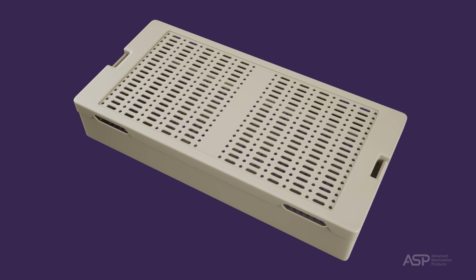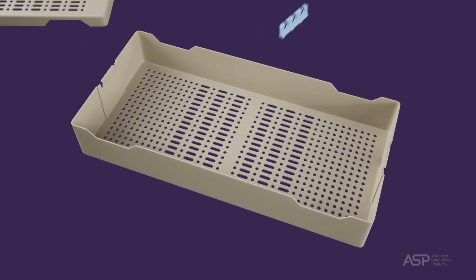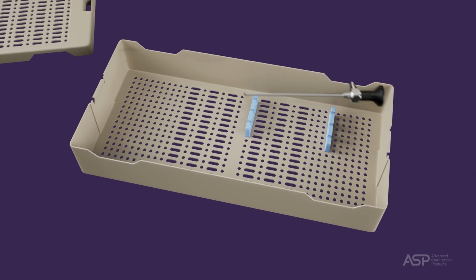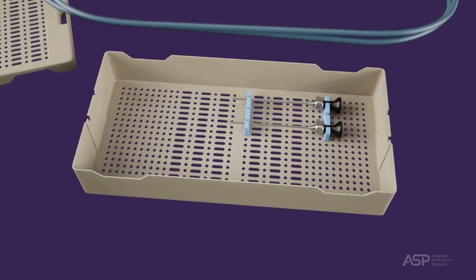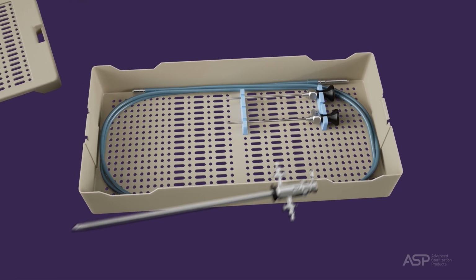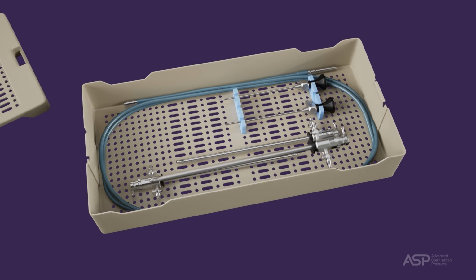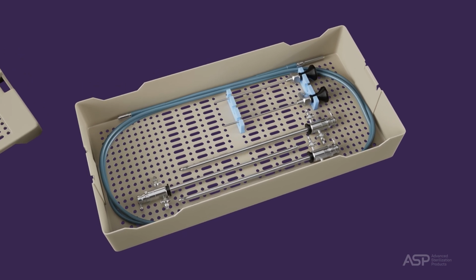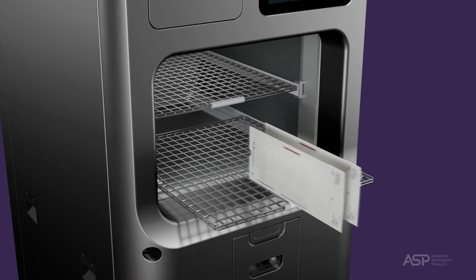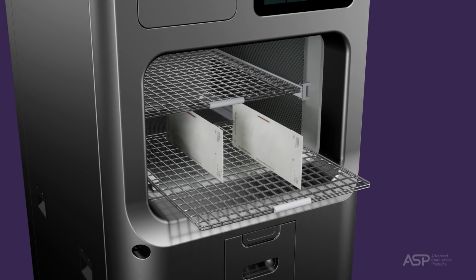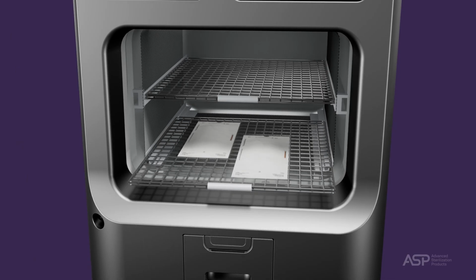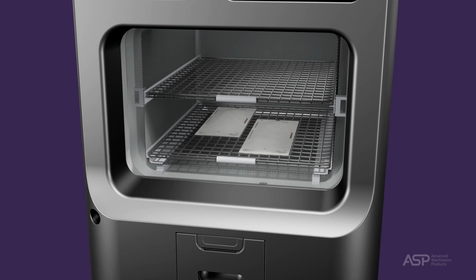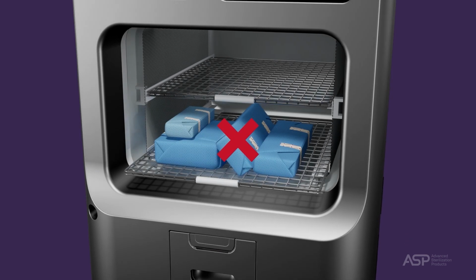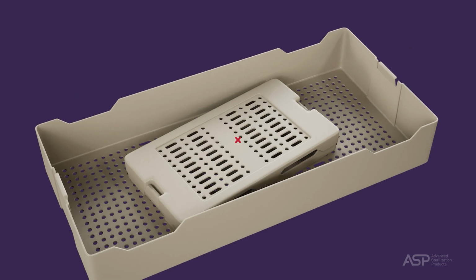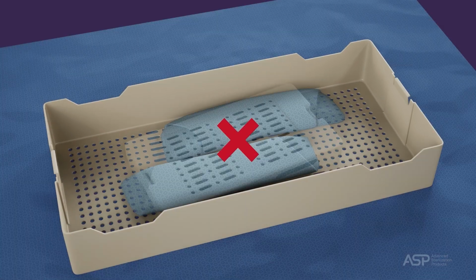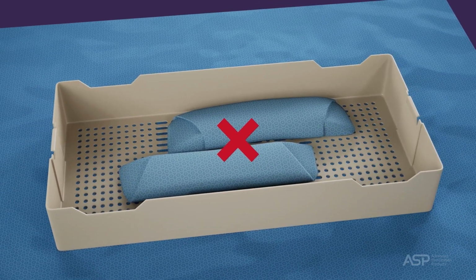Detailed information on loading and packaging can be found in your user's guide, but the following are some basic guidelines. Arrange items within a tray to ensure proper diffusion of H2O2 throughout the load. Do not stack instruments within trays or containers. Place Tyvek pouches on the edges if possible, and arrange them so that the transparent mylar side of the pouch faces the opaque side of the next pouch. Do not stack pouches and do not stack trays in the chamber. Do not place trays within trays or place wrapped instruments within wrapped trays.